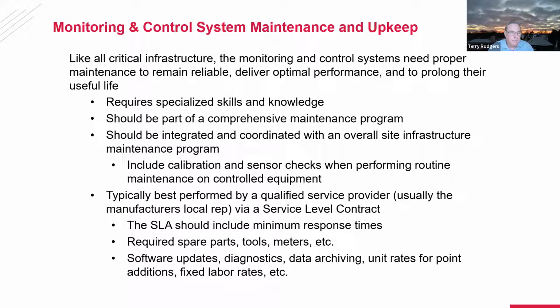So basically, you need to ensure there's calibration and sensors checked, but that becomes overwhelming if you try to do it all in one shot. I say the majority of your calibrations and sensor checks should be performed as part of the routine maintenance on a piece of equipment. So if you're going to look at a pump, make sure the pump's reporting correctly. If you look at a chiller, make sure that all the alarms and everything are done. And while you're doing these things, go out and calibrate those sensors, compare them to field measurements, and make sure everything jives and is consistent.